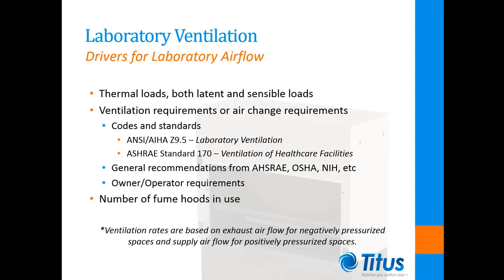ASHRAE Standard 170, which covers laboratories and healthcare spaces, sets minimum requirements for total air changes per hour, the volume of outdoor air to be supplied, and room pressurization requirements. However, it recognizes that a set ventilation rate will not meet the needs of all conditions and defers to ANSI Z9.5 as long as a hazard assessment and laboratory ventilation management plan have been established. The final component in establishing laboratory airflow rates is the volume of air used by the fume hoods, which are designed to capture and remove contaminants at the source. The volume of airflow required by these hoods will depend on the type of hood and quantity used.